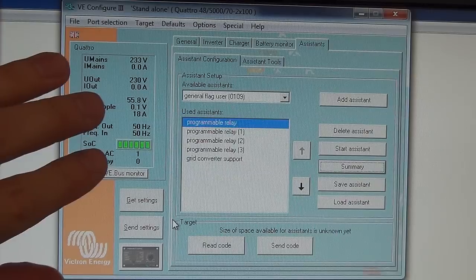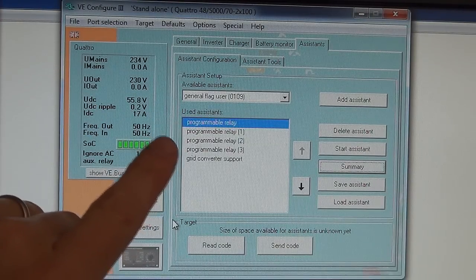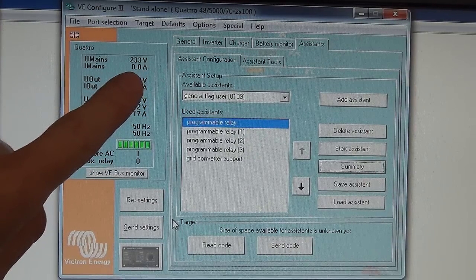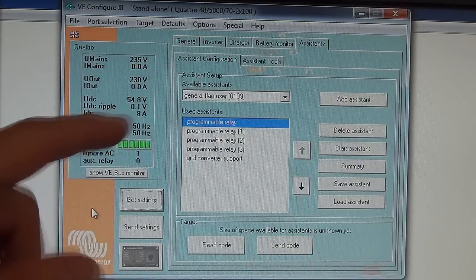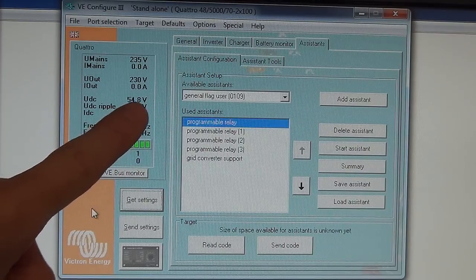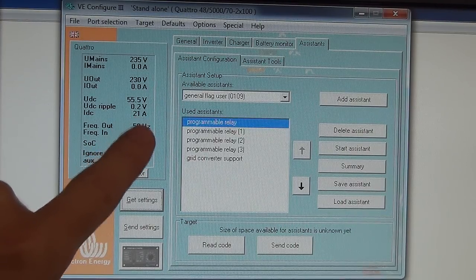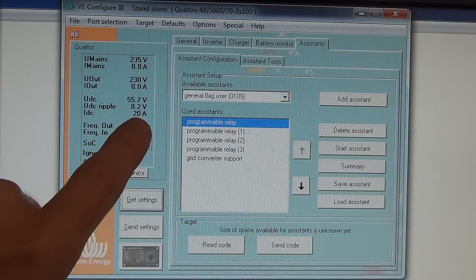This piece of software I'm showing you is generally not available to the end user of a system. This is used to configure that big Quattro inverter. The reason this isn't generally available is that any settings which aren't set correctly can damage your battery bank or system. So it's meant for engineers or professionals. I've got access to this so I've been able to set things up to make sure my system works correctly so it doesn't feed back to the grid and I can automate the usage of when batteries are used or not. It tells you what you're bringing in from your power company—at the moment there's zero amps coming in. You can see there's no power being drawn from the battery bank because all power is being supplied by the solar panels themselves. You can see the voltage of the battery bank as it's being charged, and at the moment it's being fed with about 19-20 amps, recharging from its use during last night. The house is fully running off solar power and we're charging, putting 20-odd amps back into the system.